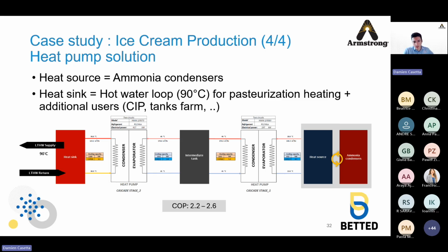And here it happened that the heat available was at a fairly low temperature, 20, 15 degrees, and that the heat needed was at a fairly high temperature, approximately 90. To efficiently provide that lift, we use the cascade, this technique that we've seen in previous slides. So by using two different heat pumps with different technologies to lift the heat in steps, so from 15 to approximately 50, and then from 50 to 90.